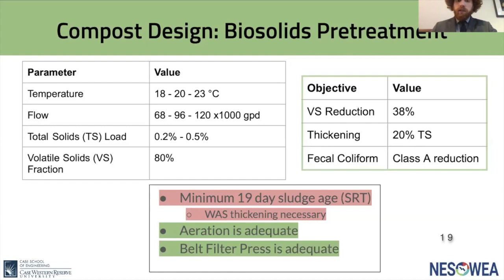When we looked at the current facilities, while the aeration is adequate in the digesters for mixing and the belt press is adequate for thickening to 20% total solids, the volatile solids will not be reduced enough in the low 6- to 12-day sludge retention time. We will need at least a 19-day sludge retention time to provide sufficient volatile solids reduction. To achieve this, instead of adding more digester volume, we are proposing to thicken the waste-activated sludge to reduce flows.